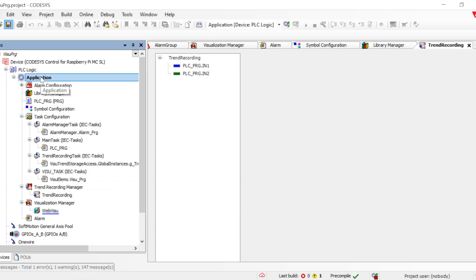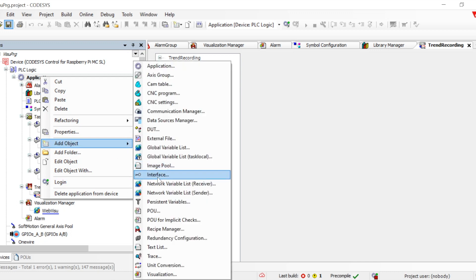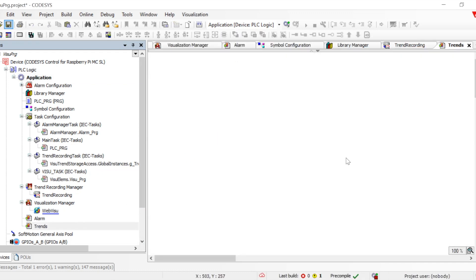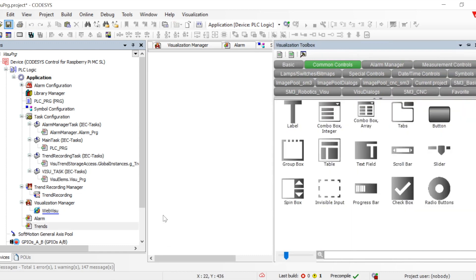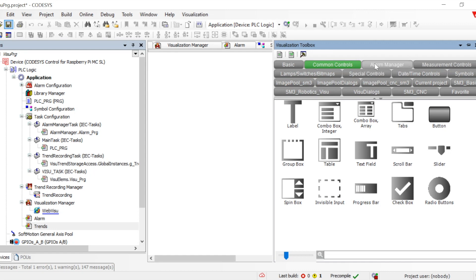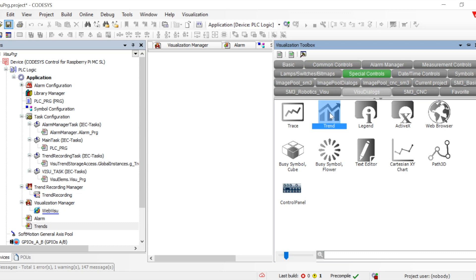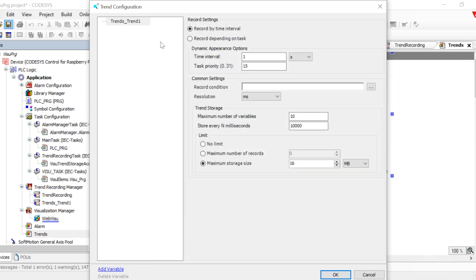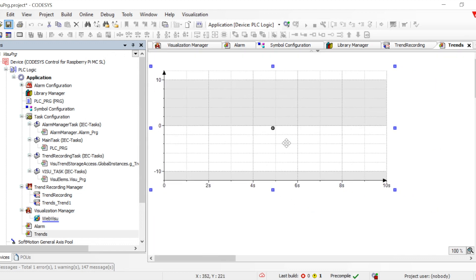Since it's a trend, we need to also visualize it. Let's add a visualization and name it. We have a graphic called Trend, and there are two different ways to add the trend: either create a visualization and go to Special Controls and drag and drop the trend — that will also create a trend recording object — or you can right-click and add the trend. Both methods have the same options.